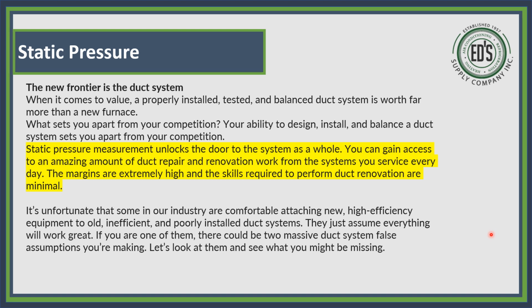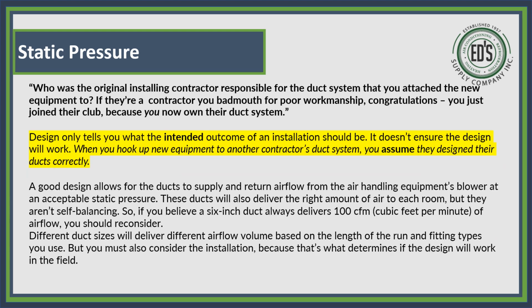The margins are extremely high, and the skill required to perform ductwork renovations is minimal compared to being a service tech. It's unfortunate that some in our industry are comfortable attaching new, high efficiency equipment to old, inefficient, and poorly installed duct systems. They just assume everything will work great. If you are one of them, that could be two massive duct system false assumptions you're making. Let's look at them and see what you might be missing.